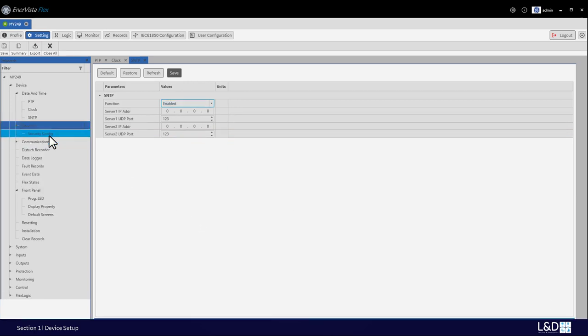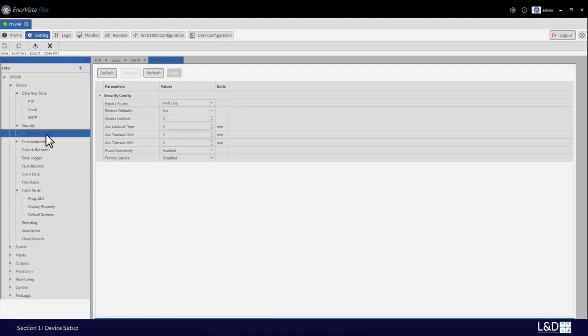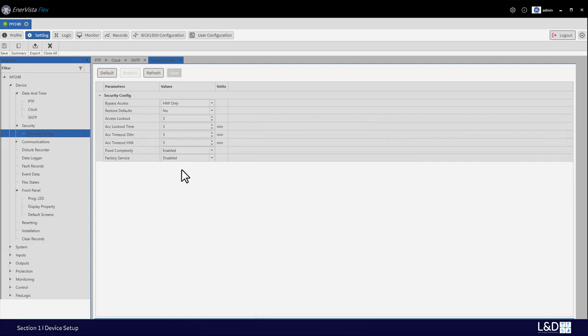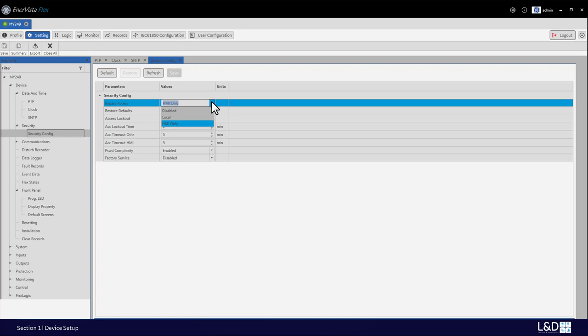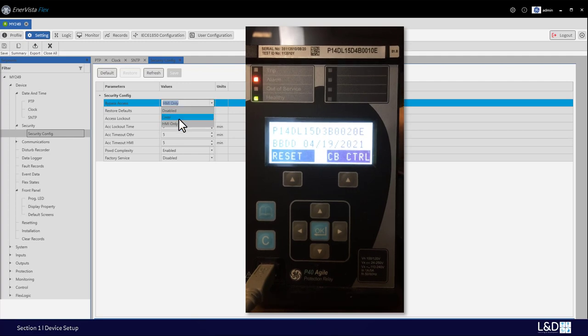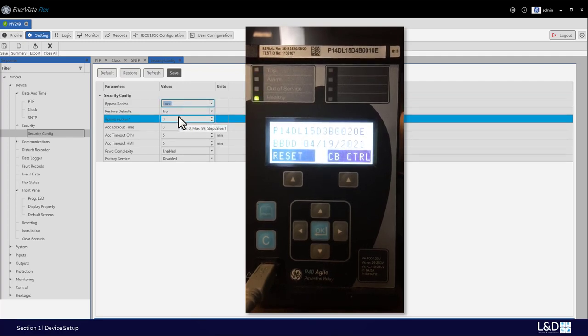Security has basic security and advanced cyber security settings for server configuration and syslog configuration, with two options based on the order code. More details will be covered in the security modules. Here we just need to know there is a bypass access control setting. If the bypass is set to HMI only, then no user authentication is needed to change the settings or reset the LED. If the user selects local, then no user authentication is needed for accessing over USB or HMI interface.